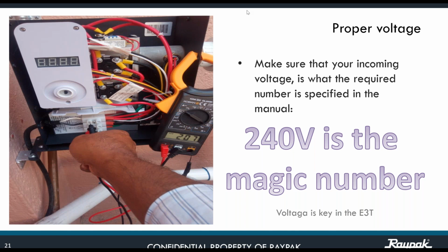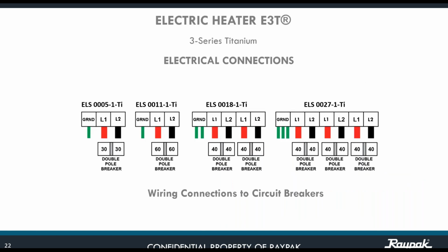See, in this test that they are doing, the complaint was, no, my unit is not working well. It's reading 207. For sure, the unit is not going to be working properly. 240 is the magic number. This is exactly how you're going to be making the connection. That particular schematic, you can find it in our manual.